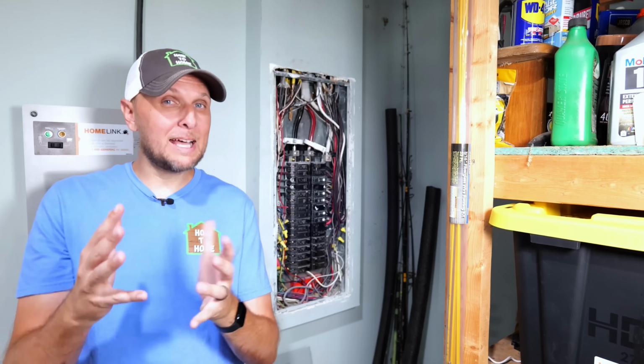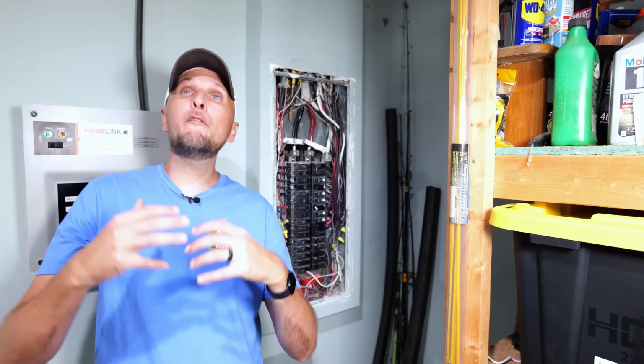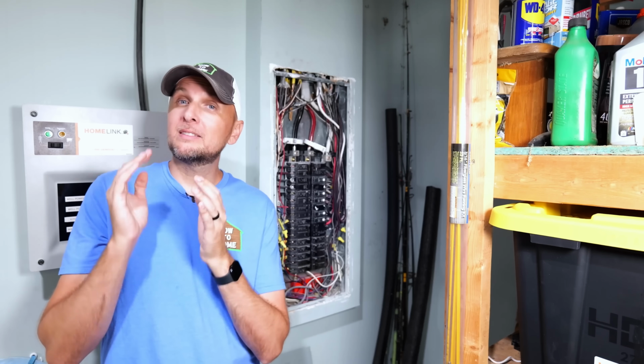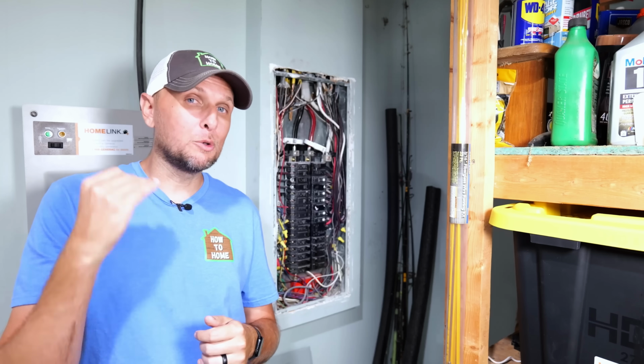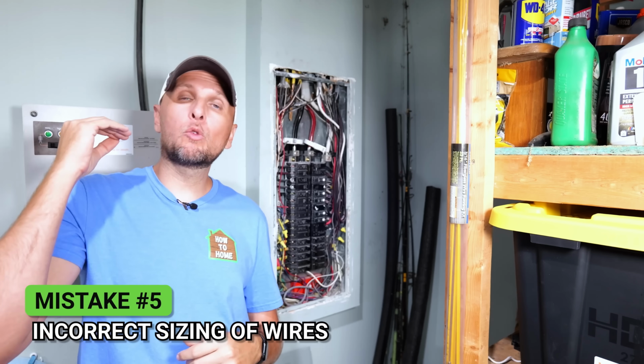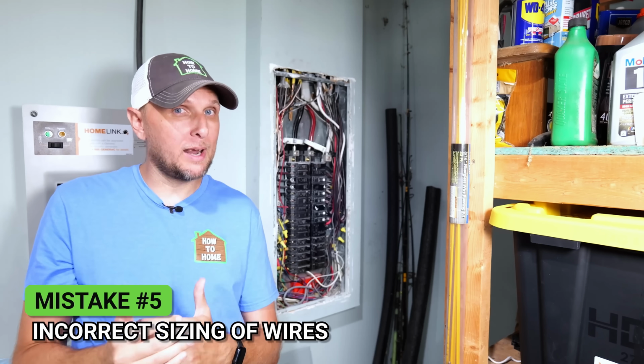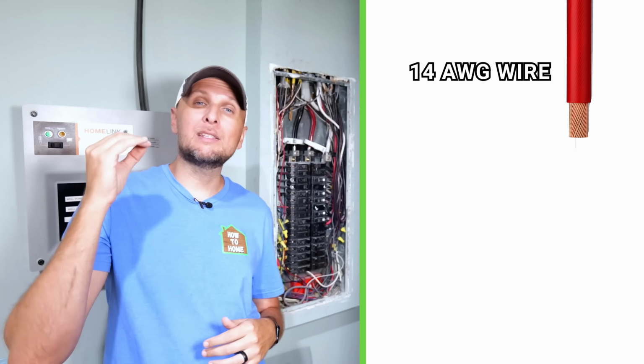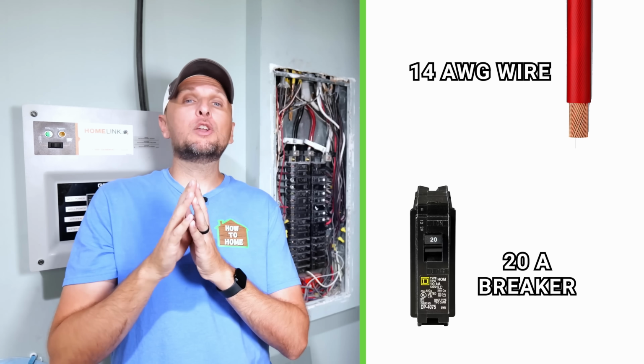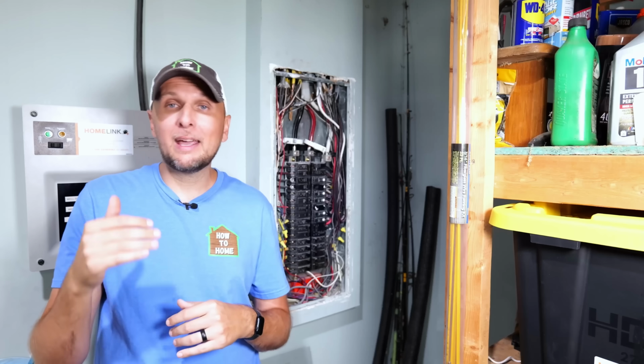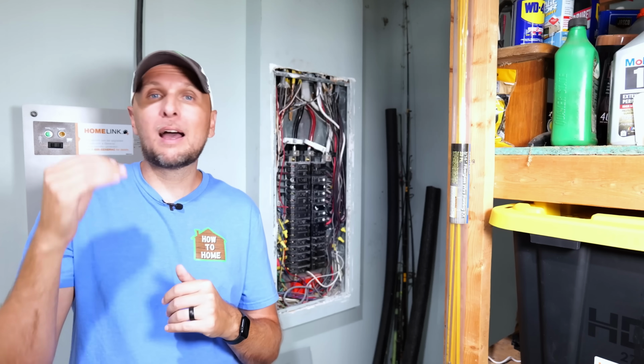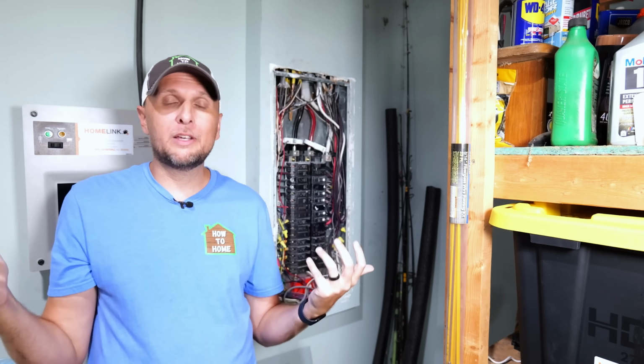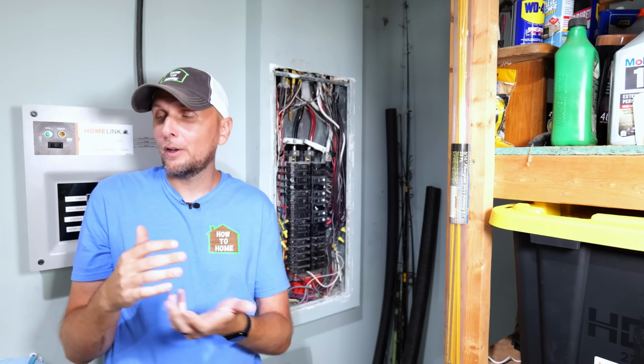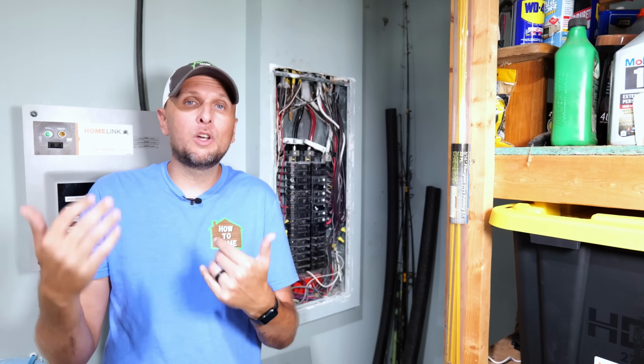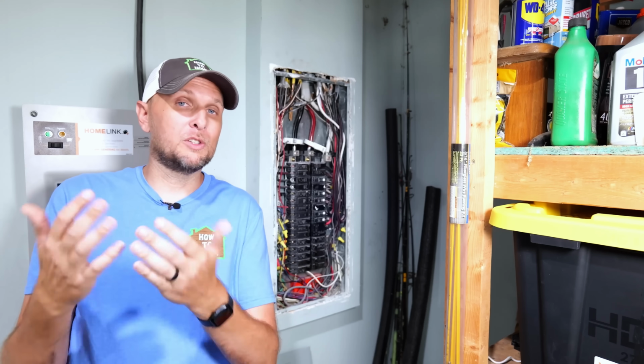All right, so for this next really big mistake, it is probably one of the most common mistakes that DIYers make, if not the most common. And that comes down to using the wrong wire gauge for your breaker. For instance, if you are trying to connect a 14 gauge wire to a 20 amp breaker, that is incredibly dangerous to do. And I can't tell you how many times I have seen where people have done this. Maybe they just have some 14 gauge wire laying around. They don't actually have 12 gauge wire and they don't understand the possible repercussions of doing that.